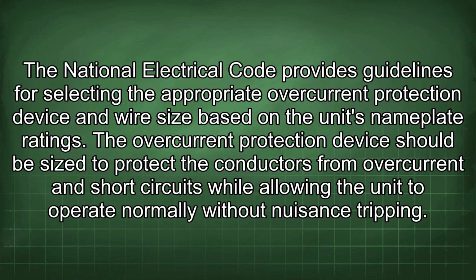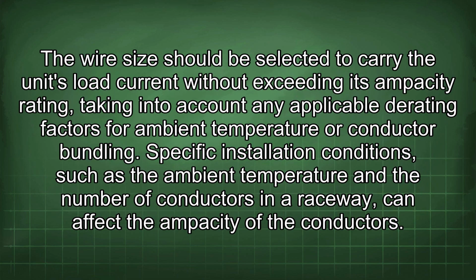The National Electrical Code provides guidelines for selecting the appropriate overcurrent protection device and wire size based on the unit's nameplate ratings. The overcurrent protection device should be sized to protect the conductors from overcurrent and short circuits while allowing the unit to operate normally without nuisance tripping. The wire size should be selected to carry the unit's load current without exceeding its ampacity rating, taking into account any applicable derating factors for ambient temperature or conductor bundling.